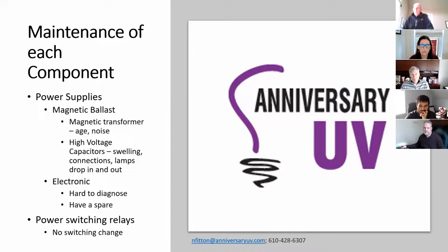Magnetic ballasts have a bank of high capacity, high voltage capacitors, and we need to keep a close eye on those. Typically, when you inspect them, you're looking for swelling and making sure the connections are all working together. They are jumped in parallel, usually 3, 4, 5, 6 of them. We want all the connections to be good, because if you lose a cap, your overall power goes down, and you may experience lamps starting to drop in and drop out. They fire, they drop out, they fire, they drop out.